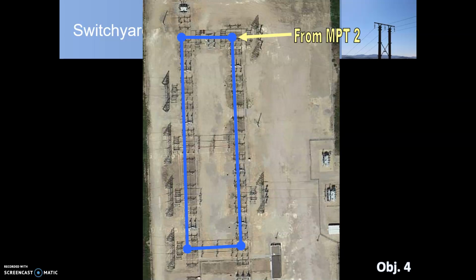What you'll notice in this particular picture is that in the upper left-hand corner, you'll see one of our transformers that feeds the 138 kV switchyard. That transformer is transformer 81. If you apply the thumb rule of 5, you can determine which 138 kV bus it feeds. Transformer 81: 1 and 81, plus 4 equals 5. Therefore, transformer 81 feeds 138 kV bus 4.